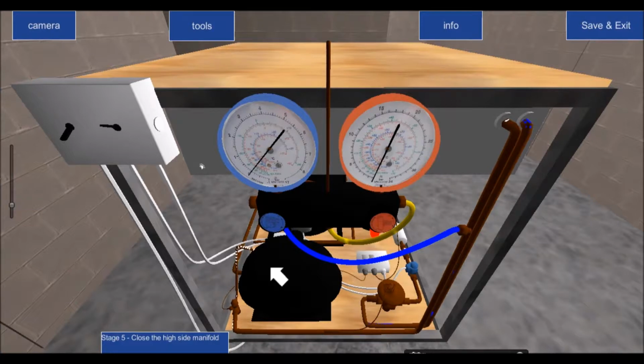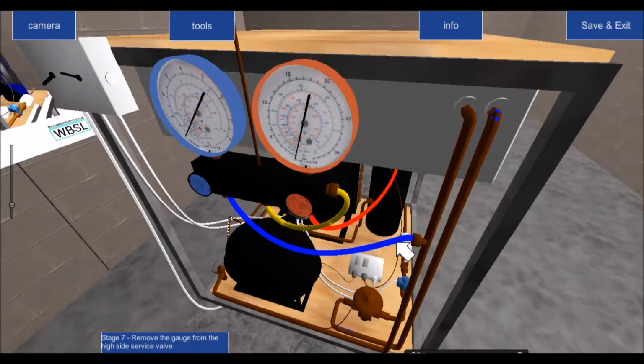So effectively now, the noise that you were hearing in the background, if I turned up my volume again, you will find is no longer there, because the compressor is no longer running. It's been switched off or de-energized, or whatever way you want to put it. The 220 volt contact is open via the pressure switch, and therefore the power supply to the compressor is killed. Okay, now before I take off my gauges, I'm going to close my high side manifold, and then I'm going to close my low side manifold. By having the two shut-off valves closed, I am now able to remove the gauges from my system.